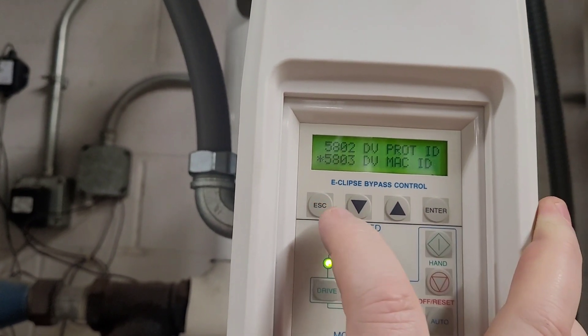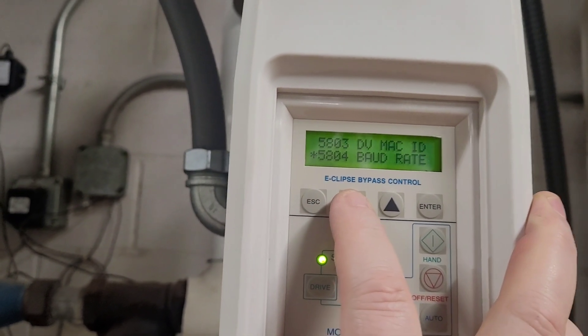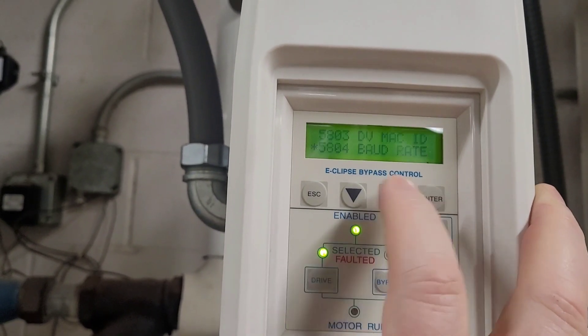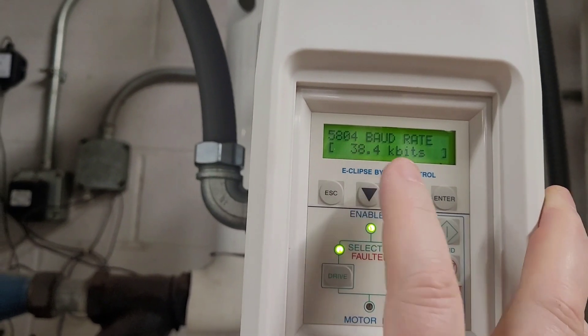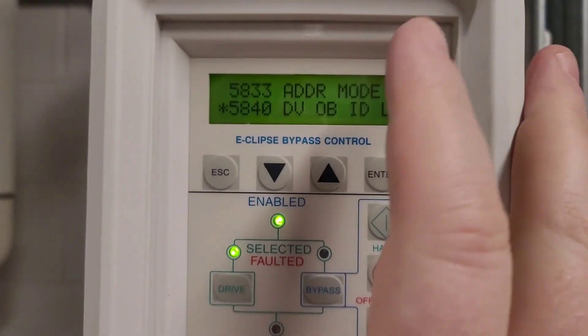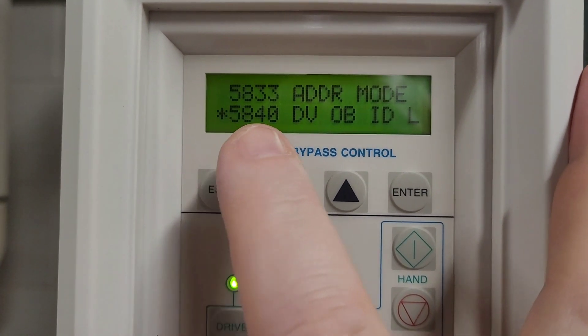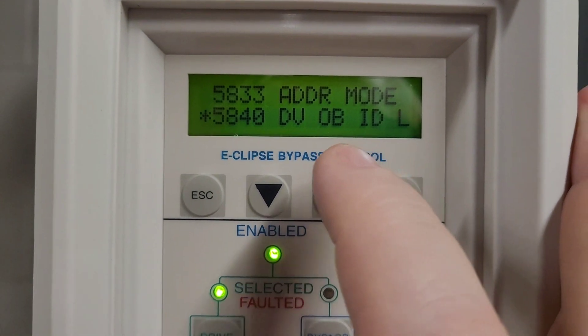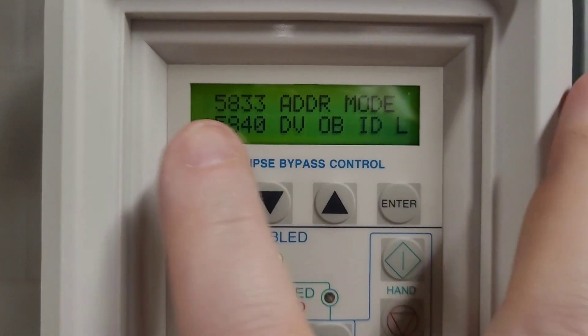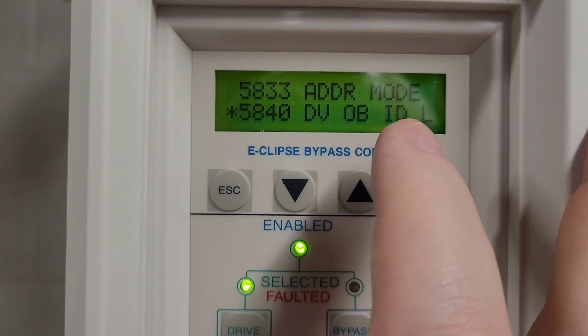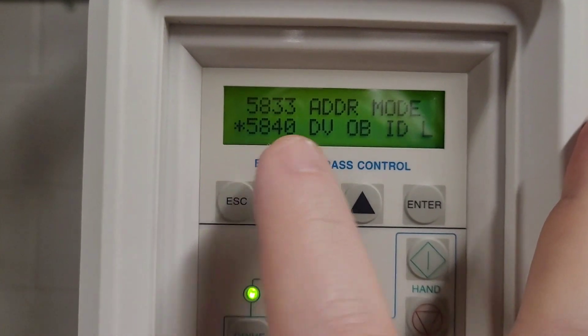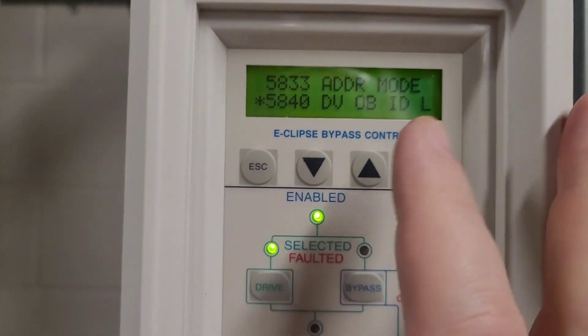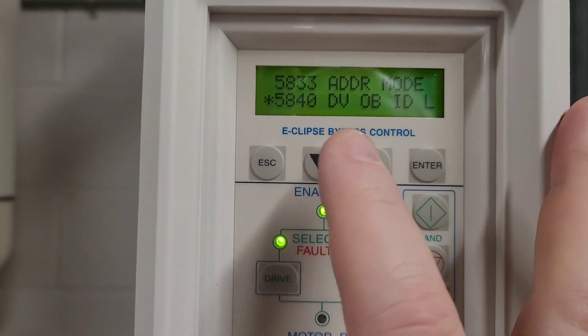I now have 26, so I press Enter. You also need to make sure of your baud rate — parameter 5804. Whatever your trunk is communicating at, that's what you need to match. 38400 is the default, which is correct here. Then go up to parameter 5840, which is your BACnet instance ID. Set that value and make sure there are no conflicts with any other instance IDs on your network.